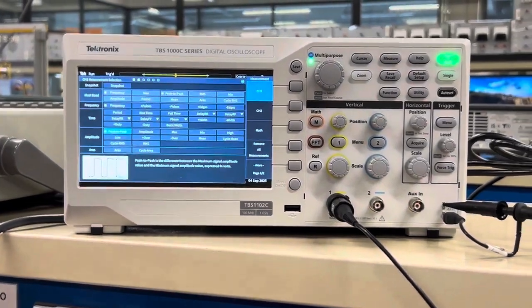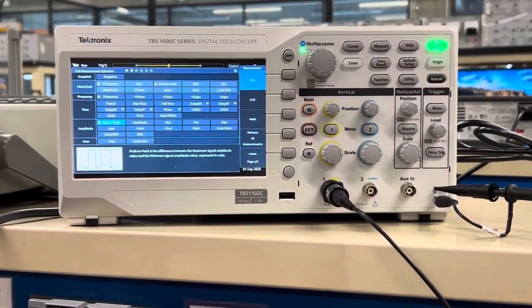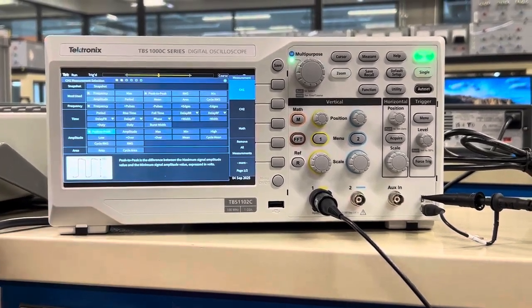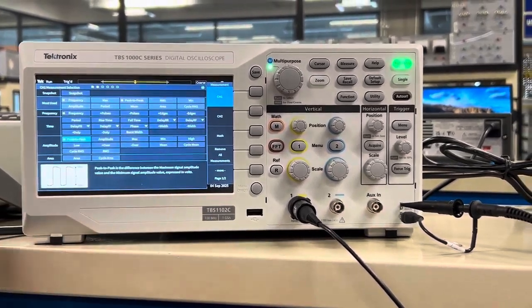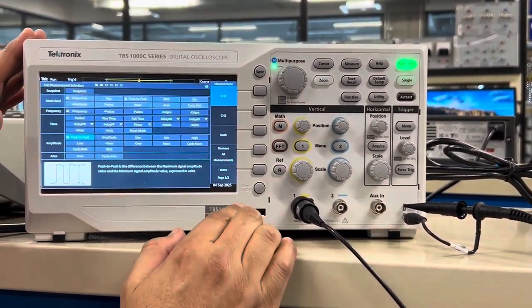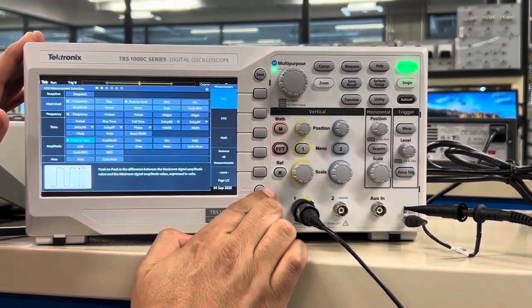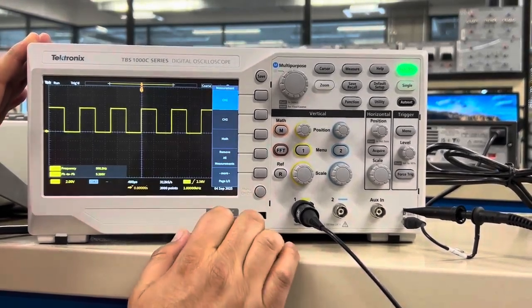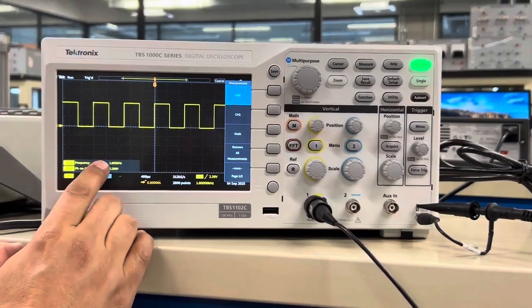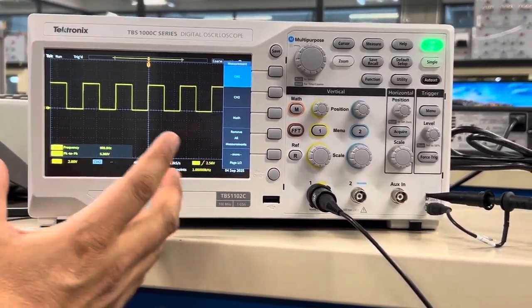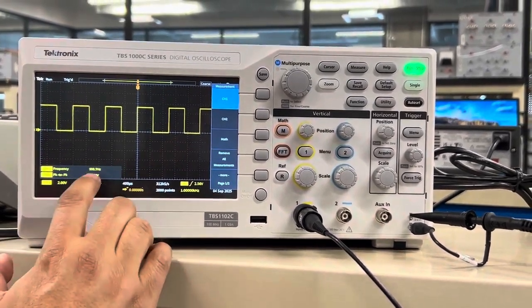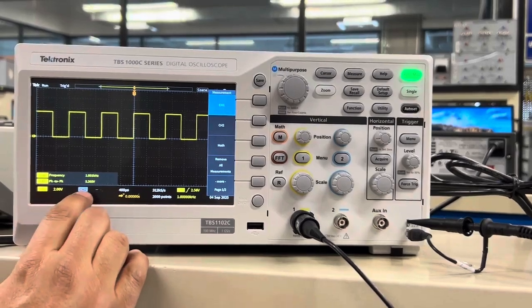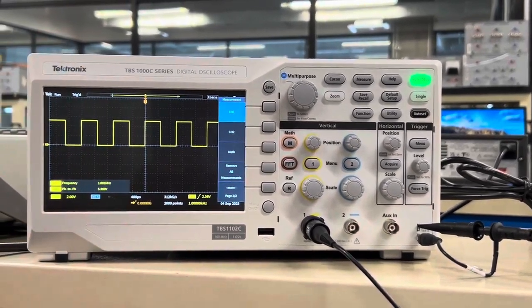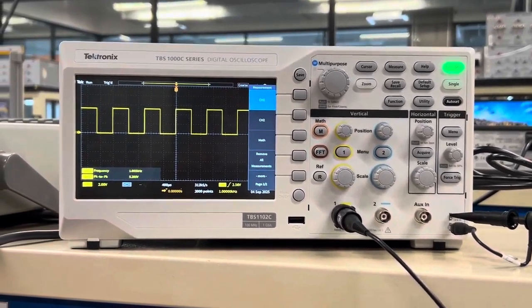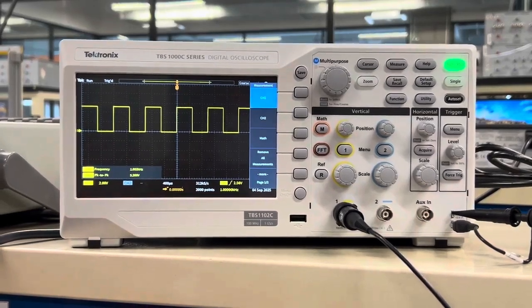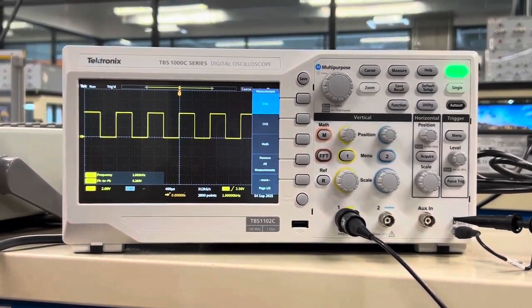Now, frequency and peak to peak have the yellow square, that means that those two measurements are going to be shown for channel 1. We will go to those buttons to the right of the screen. The round one says menu on off. We'll press it once. And now, besides the signal, we can see on the bottom left of the screen that has the grid, that the frequency is indeed 1 kilohertz, and the peak-to-peak voltage is around 5 volts.